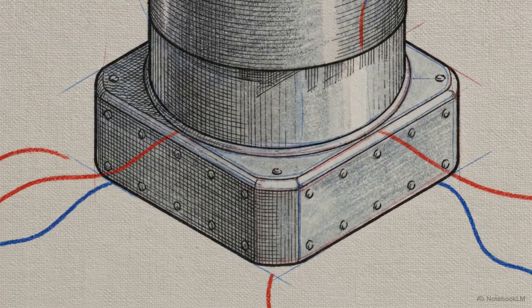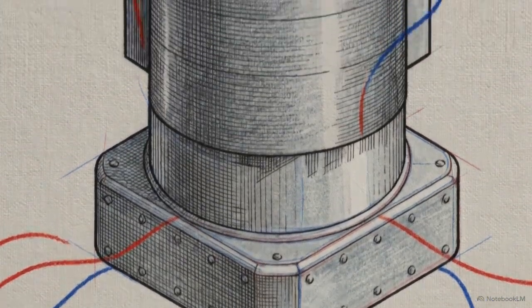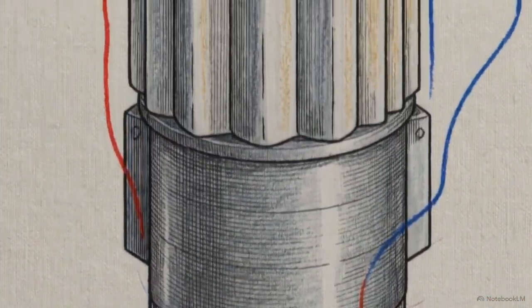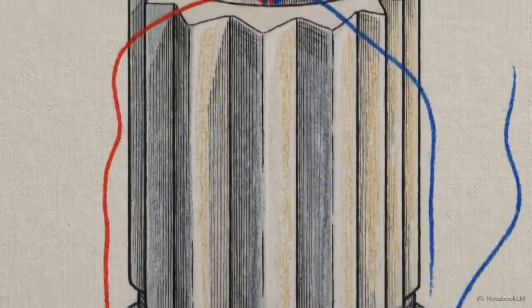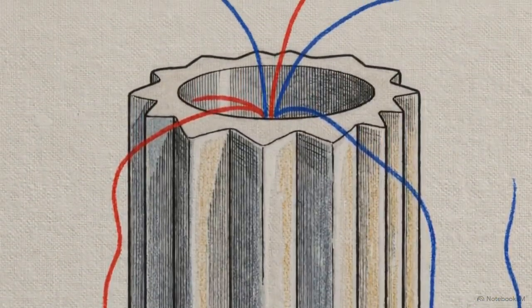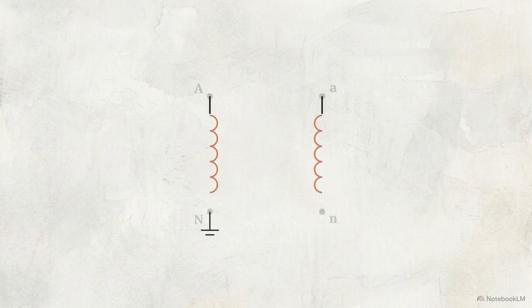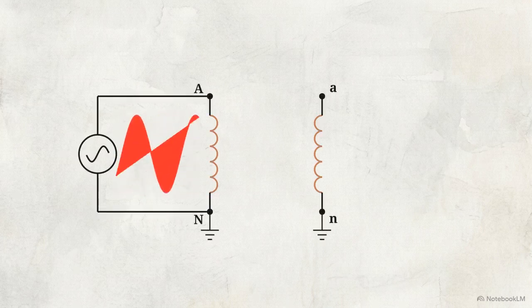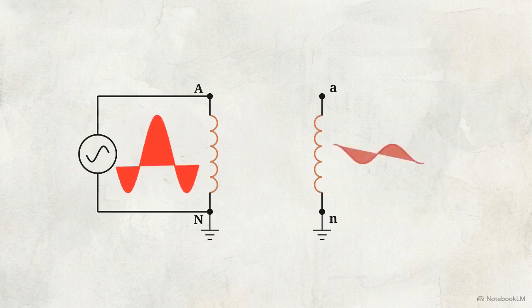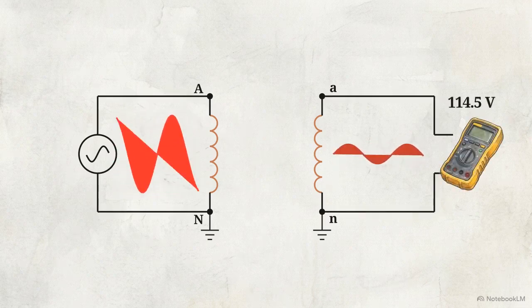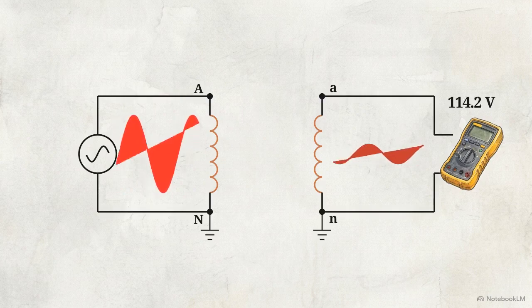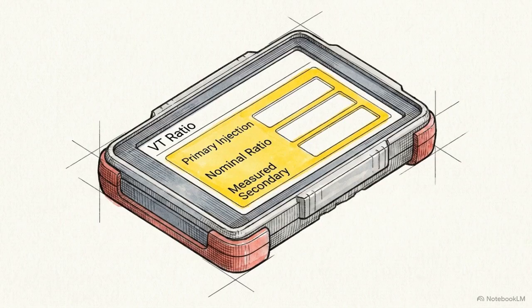Moving past static DC resistance, the sequence evaluates the transformer's dynamic alternating current behavior, specifically its electromagnetic step-down ratio. This logical schematic illustrates the process. Inject a precision AC voltage into the primary winding while simultaneously measuring the resulting voltage generated on the isolated secondary winding. This interface layout shows the CPC-100 test card, where the operator enters the nameplate ratio parameters and specifies the expected secondary output voltage for the system to track.